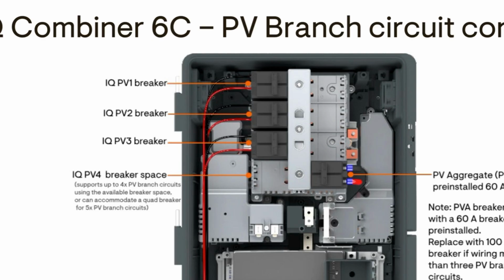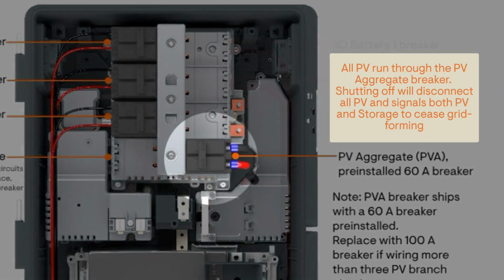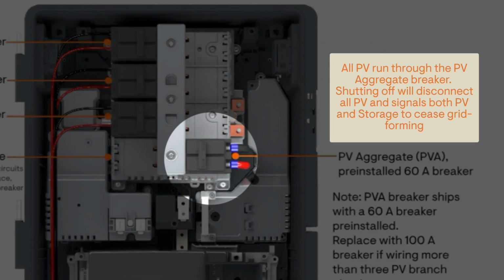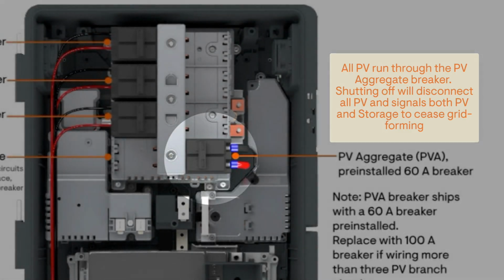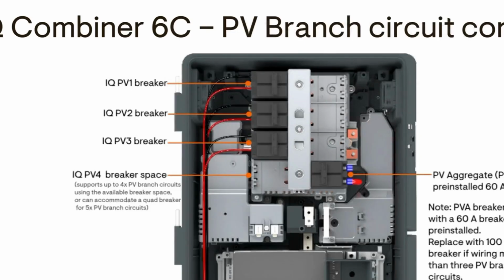combiner PV ports. All the PV production is measured by built-in current transformers, which are pre-installed and wired onto the PV electrical bus. Located on the right side bus is a pre-populated 60 amp PV aggregate, RSD breaker. The breaker must be sized up if PV capacity is above 60 amps. The maximum breaker size is 100 amps.